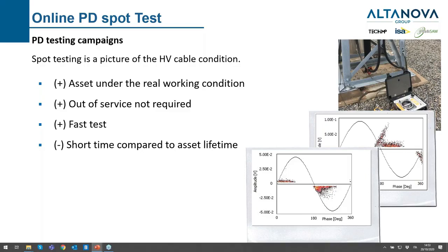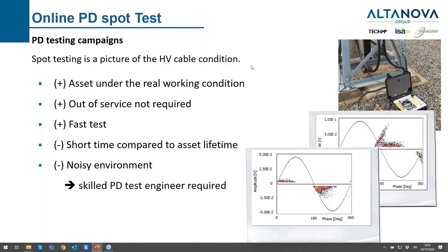The only drawback is that we are just picking up a single frame of the full lifetime of the asset. It's easy and cheap to perform, but we are losing most of the asset lifetime information. We also work in a noisy environment — especially in outdoor substations, where we can have many disturbances coming from the grid. Some skills are required to properly identify the PD sources in such conditions.